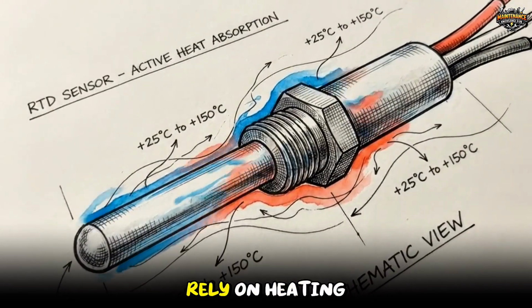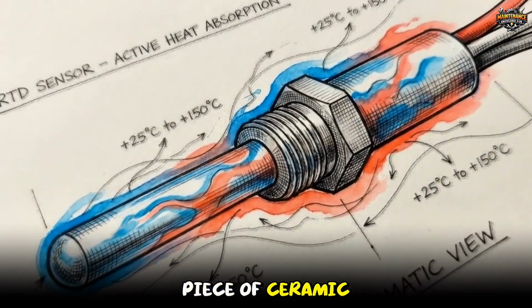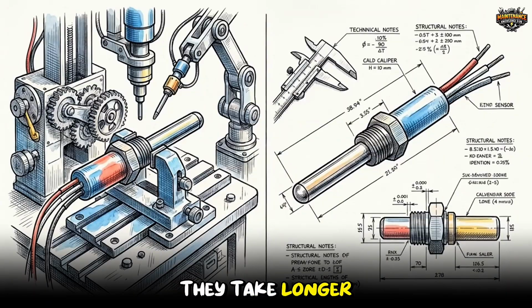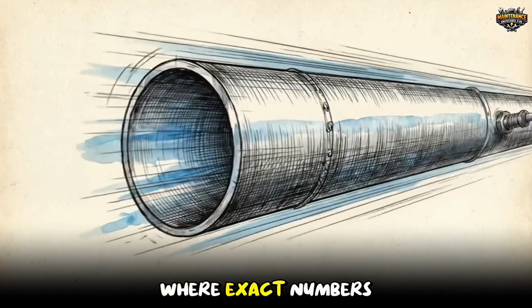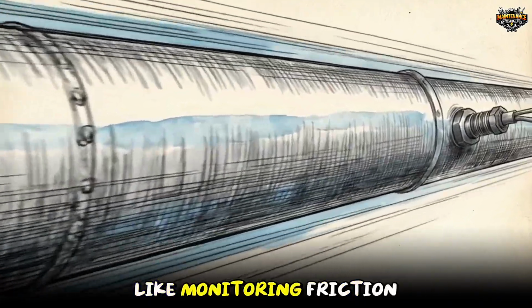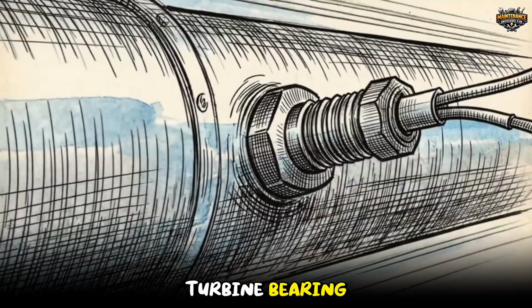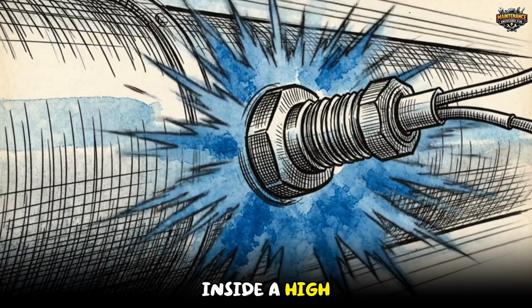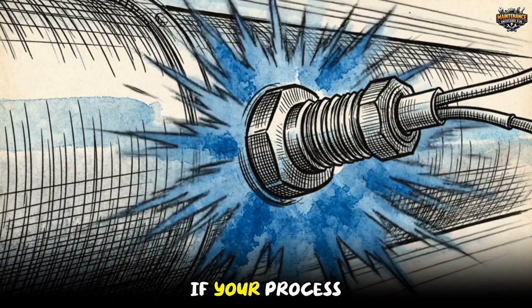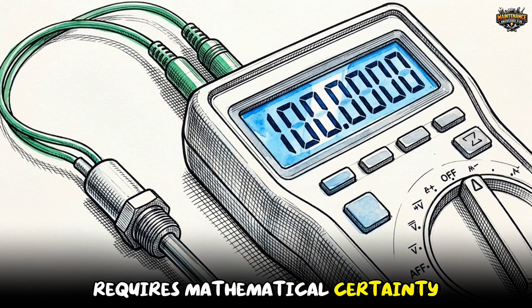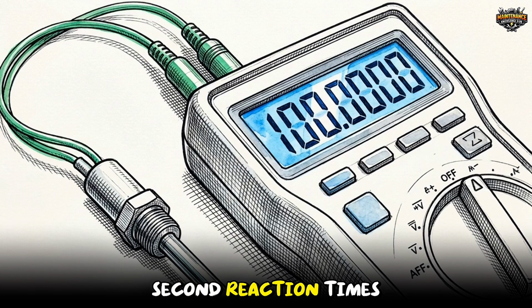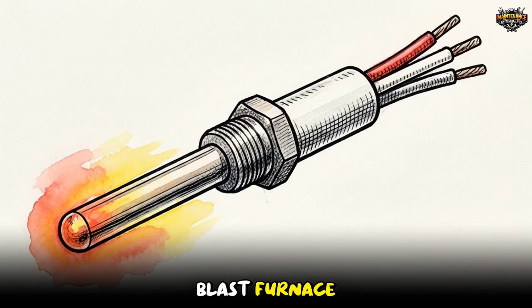But because they rely on heating up a solid piece of ceramic and metal, they take longer to react to sudden thermal spikes, and they cost a bit more to manufacture. You'll find them where exact numbers matter most, like monitoring friction heat on a turbine bearing, or tracking flow inside a high-pressure steam line. If your process requires mathematical certainty rather than split-second reaction times or surviving a blast furnace, the RTD is your standard tool.